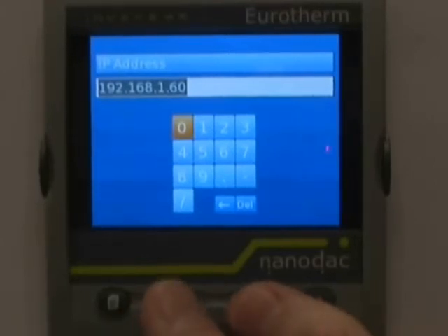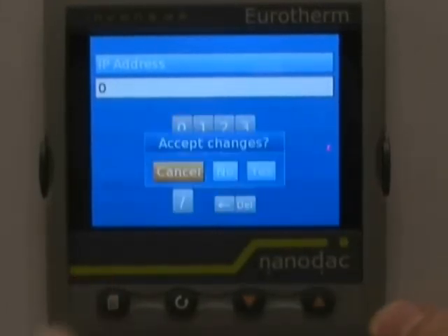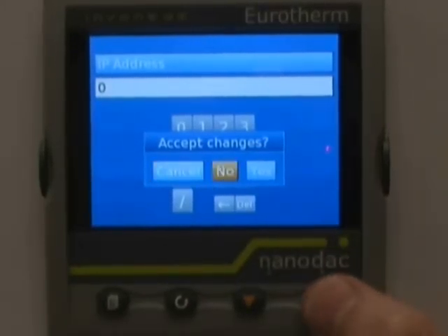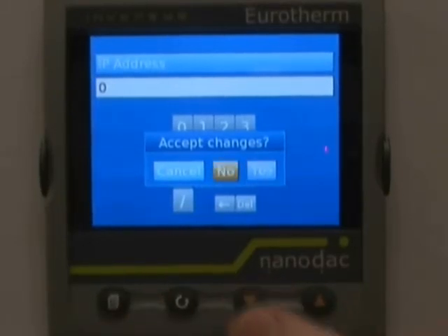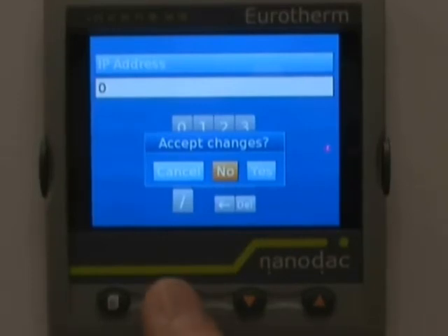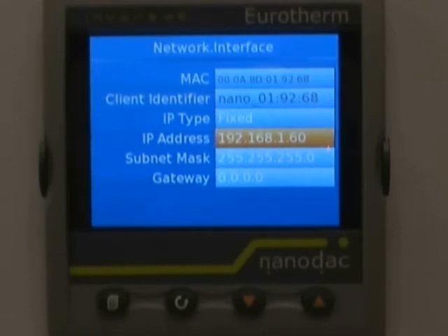Once you're done entering the IP address — I'm not going to enter it all here for interest of time — hit the page key once and it will bring up the accept changes screen. Click Yes and hit the scroll key. For demonstration purposes I'm going to select No. What we have just done is change the fixed IP address of this NanoDAC recorder on your network; for demonstration purposes we have 192.168.1.60.